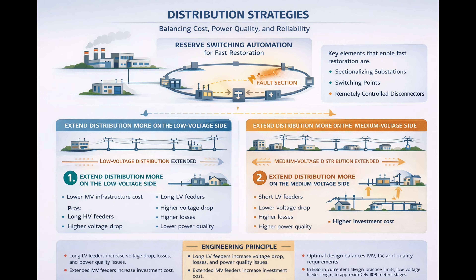The choice between more medium voltage distribution and more low voltage distribution affects investment cost, technical losses, voltage stability, and reliability. As an engineer, you must evaluate load density, distance, and required quality of supply. If you extend low voltage too far, voltage drops become unacceptable. If you extend medium voltage too far, infrastructure cost rises significantly. Optimal design requires balance. Network configuration, switching capability, feeder lengths, and voltage must be considered together.